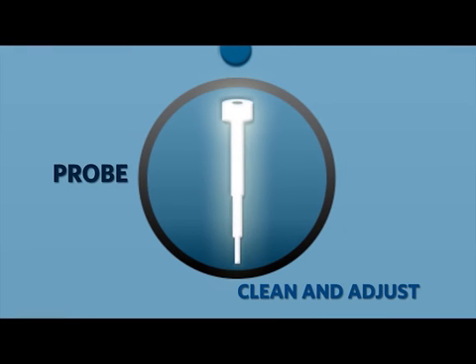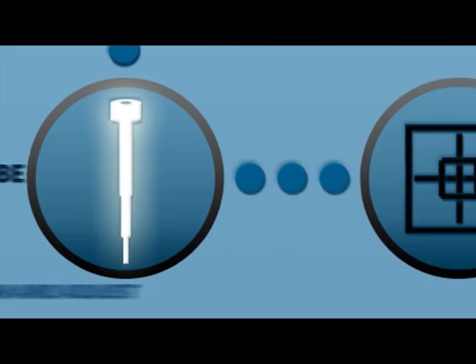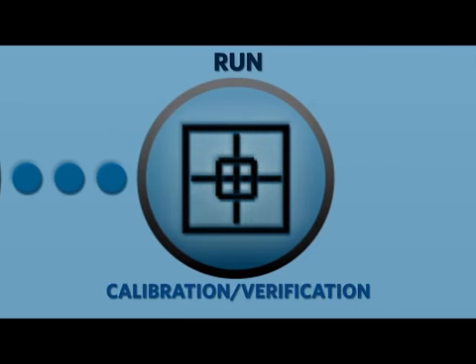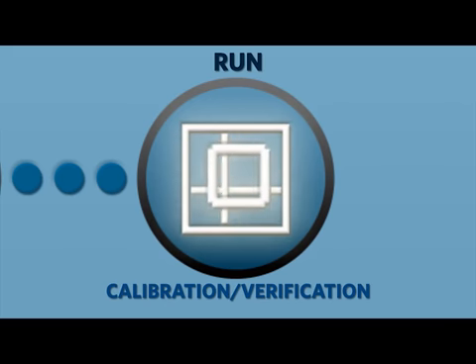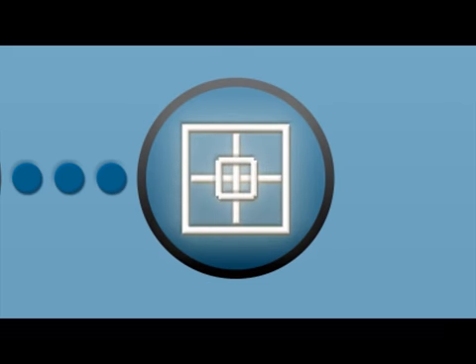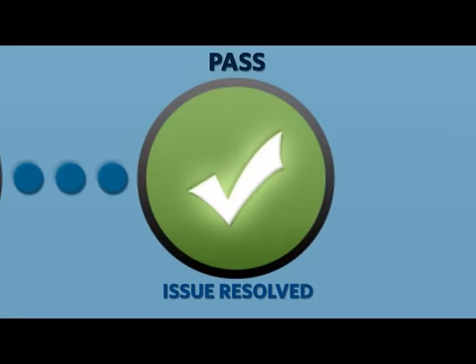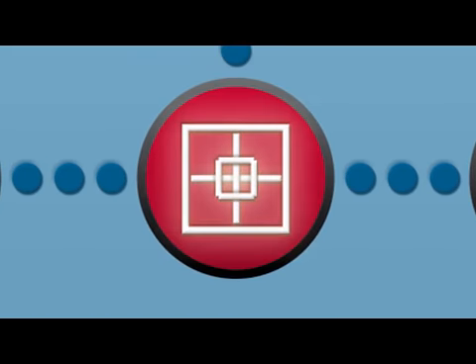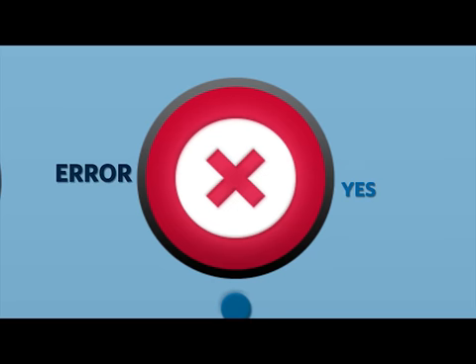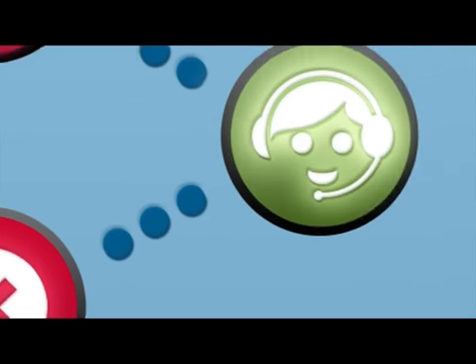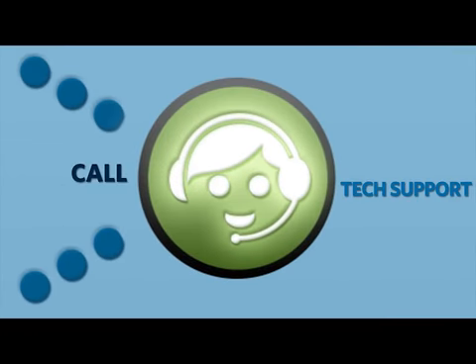Once the sample probe height has been set, run a system clean using sodium hydroxide. For detailed instructions on how to run the system clean function, use the Run System Clean video. This will resolve most clog and verification issues. After the probe height is set and a clean cycle is performed, running a calibration and verification cycle will show if this step was successful. If this step didn't resolve the issue, then advanced troubleshooting will need to be performed on your MagPix instrument. Having completed these steps will allow Luminex technical support to start advanced troubleshooting immediately.